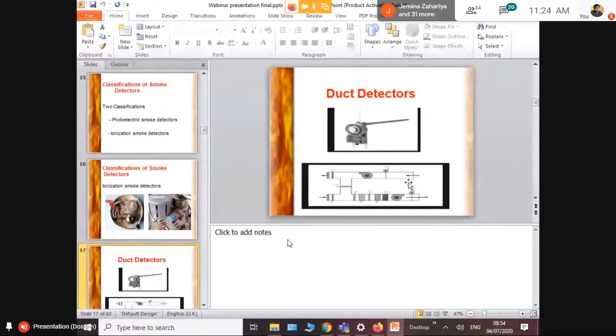This is how the air comes in for HVAC equipment. Wherever you have ACs in shopping malls, you would have seen diffusers. This is the diffuser which gives you the airflow, and this is a fan, and here you see the S. This is a smoke detector. It will have a punched-in sampling tube here. When the air comes from here, in case it has an addition of smoke to it, this will sense it, and it will give a signal to the control room.